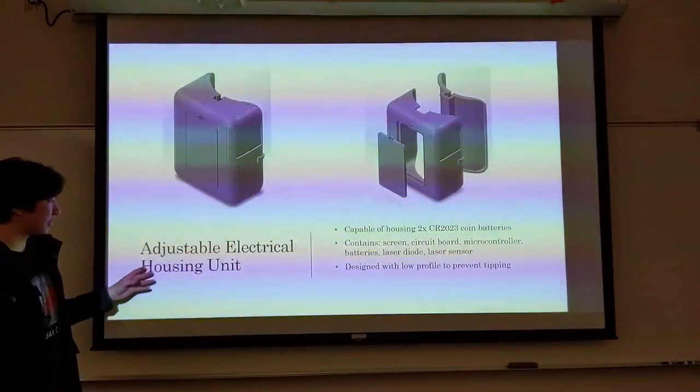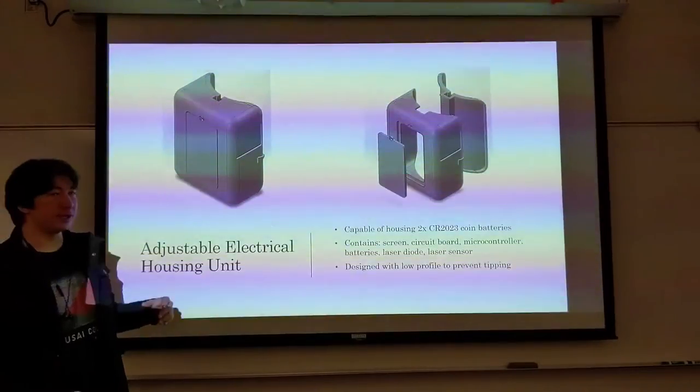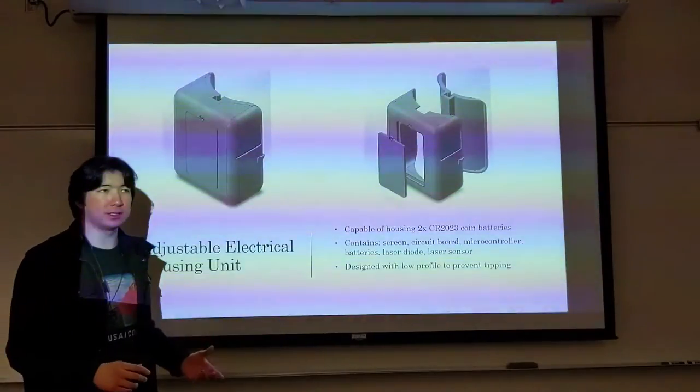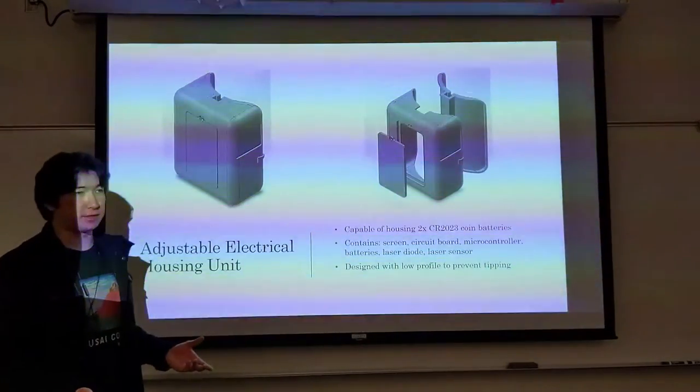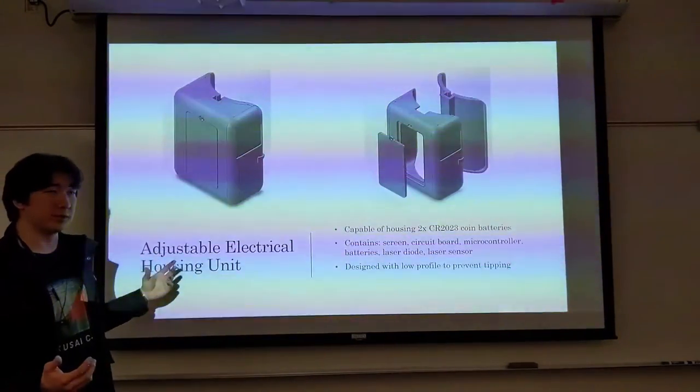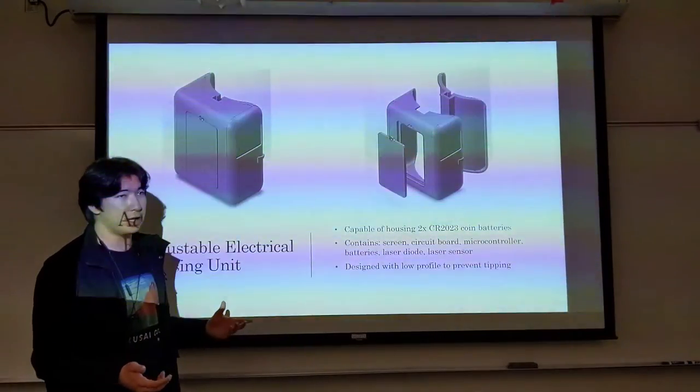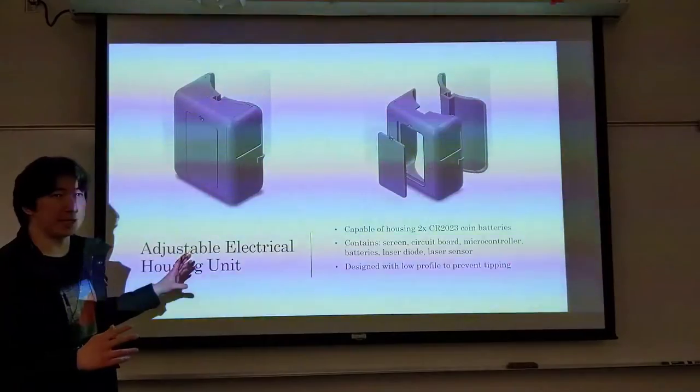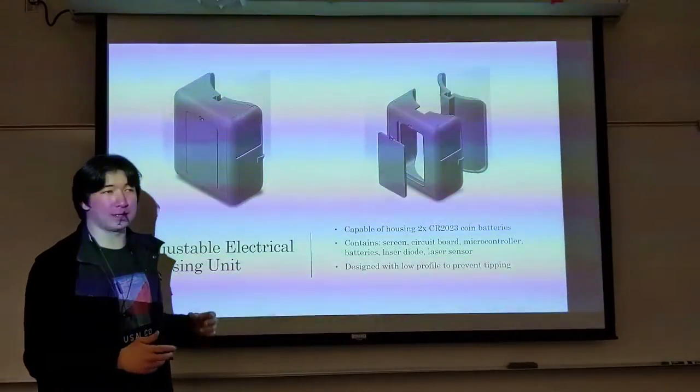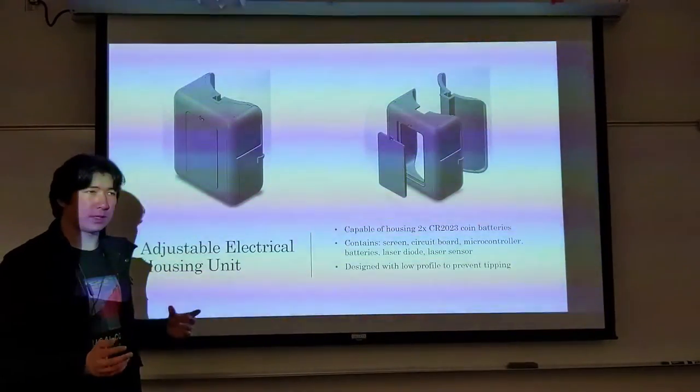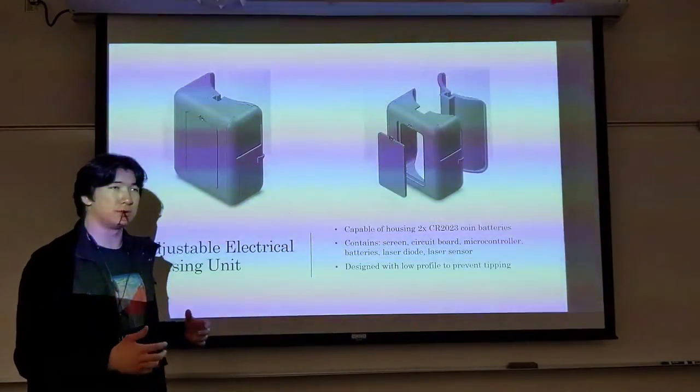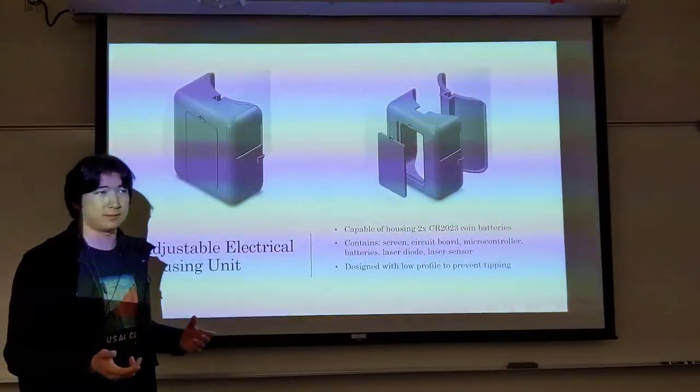Here we have our adjustable electrical housing unit. The initial prototype that Carrie showed to us was very blocky overall, and while small, didn't seem to really fit with the overall design of the spirometer. Here I've been redesigned to have a low profile, to be more cohesive with the overall design of the spirometer. Since it has a low profile design that matches well with the spirometer body, in the case of heavier units with perhaps larger batteries or heavier electronic circuits built into it, there won't be any issue of tipping, as the whole spirometer is quite light and plastic.